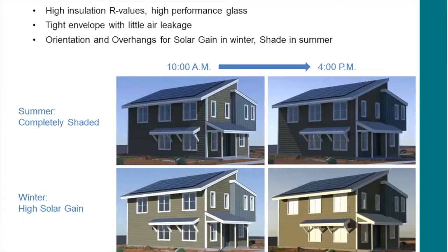So the secret sauce is there's no secret sauce. The whole package was designed holistically, trying to get a lot of details right, starting with the fundamental design. We have a really efficient, really small HVAC system because the envelope is so tight and well insulated, because we oriented it east-west, and used slightly higher solar heat gain coefficient glass, triple pane all around, 0.16 U-factor windows. We also use double stud walls, ours are 9¼ inch cavity depth, fully filled with cellulose, and R-60 in the roof.